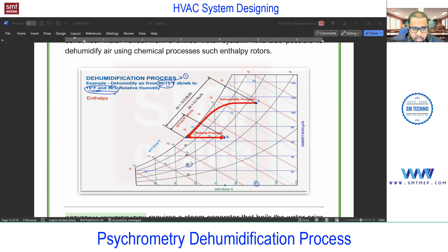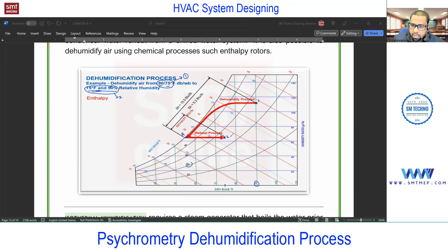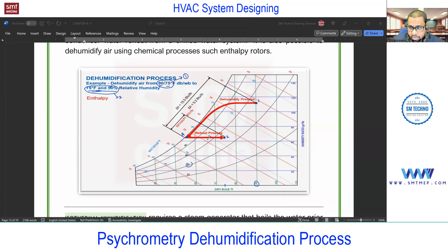The path goes from point 1 to point A, then from A to point 2. Point 2 cannot be achieved directly with cooling alone. First, we over-cool the air so we can extract more and more moisture, decreasing the humidity ratio. After that we add sensible heat to increase the dry bulb temperature, which increases the holding capacity and effectively decreases the RH to the target.